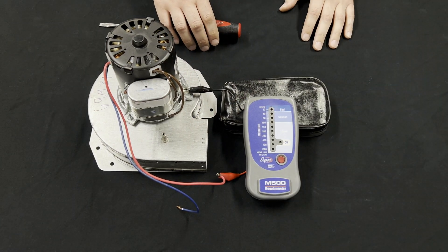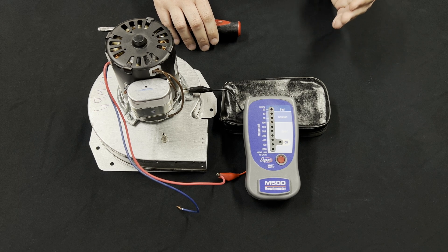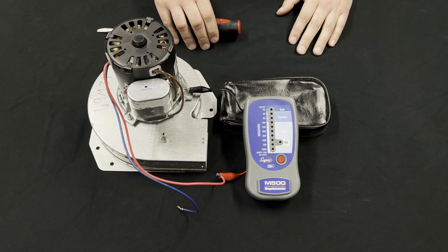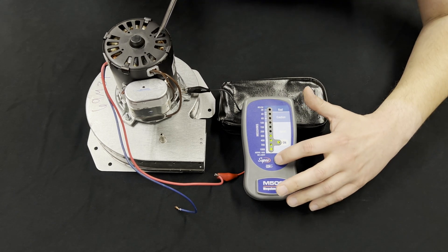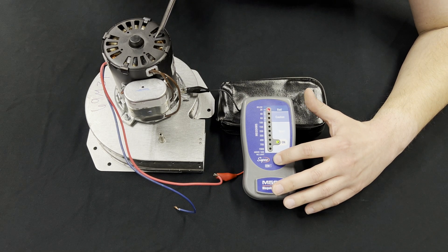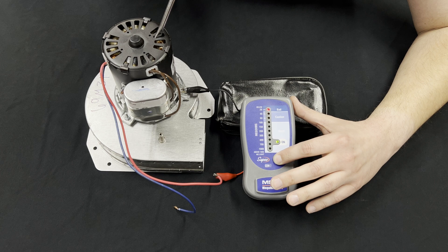To simulate what it would look like if the insulation had broken down and was coming in closer contact to the frame or ground of the case, I'm going to put this screwdriver in here and touch between the winding and the case to show that the insulation reads as bad.